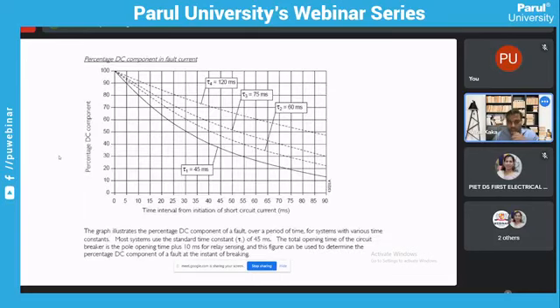Now, this is just a graph of the percentage DC component in the fault current. Normally, all our breakers are tested with an X by R ratio of 14. That comes with a tau value of somewhere around 45 milliseconds. Now, this 45 millisecond comprises somewhere around 35 or 40 milliseconds. Along with that, when we are reaching a 45 millisecond tau value, the further critical parameters in reaching this particular graphical value also depend on the breaker opening time and your response time.